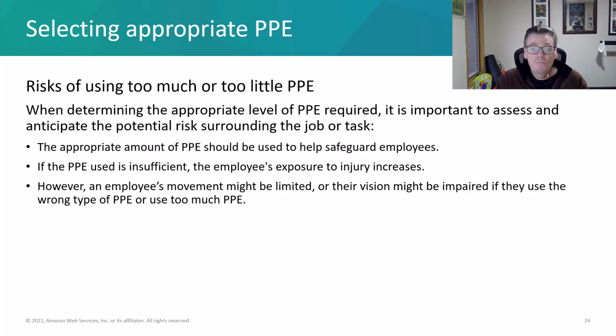If we don't use proper PPE, the employee's exposure to injury can increase. Here's an example. Your safety engineer goes in and does some decibel readings. Okay, how loud is it? Then they look up some of the PPE standards that OSHA has, for example. OSHA says after a certain decibel level, hearing protection has to be used. So we can go in and monitor in the data center where the decibel levels exceed that, and then require that employees use hearing protection in those locations.